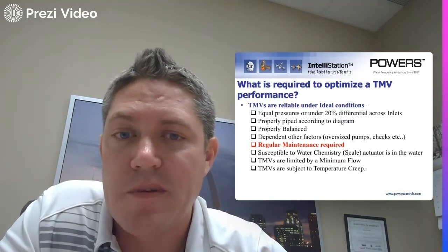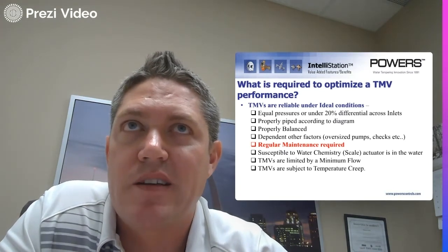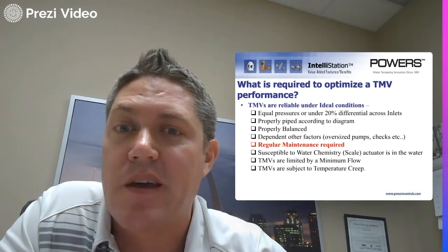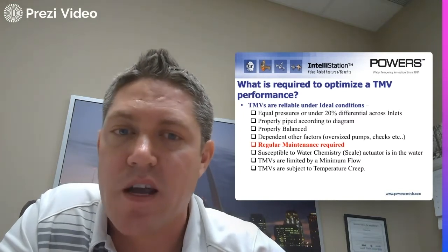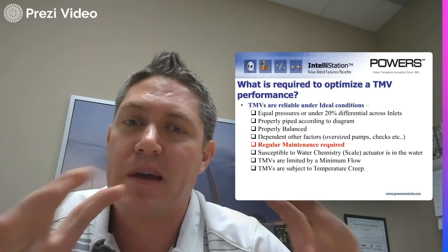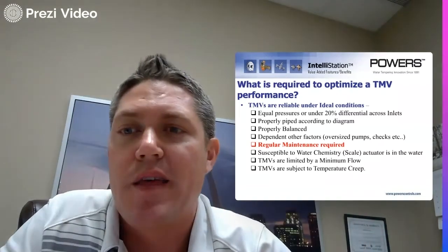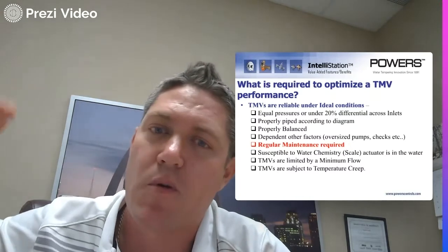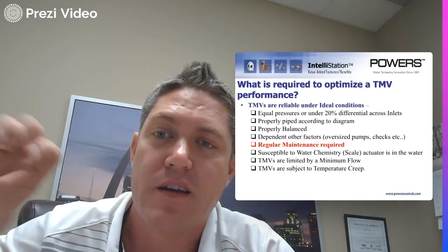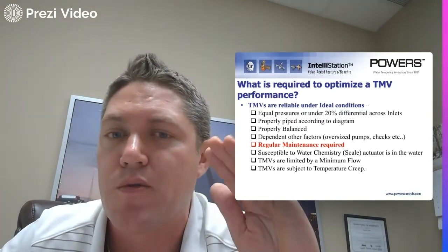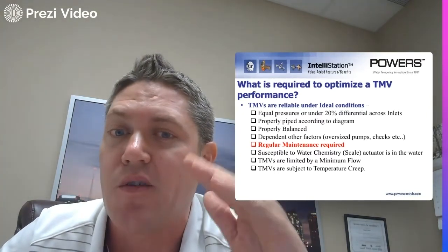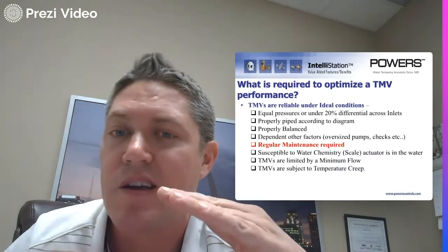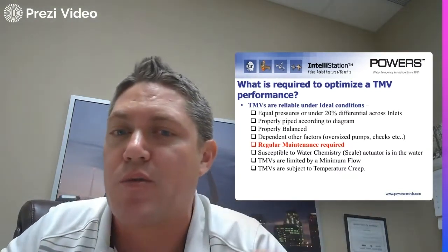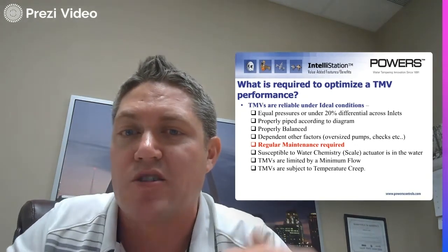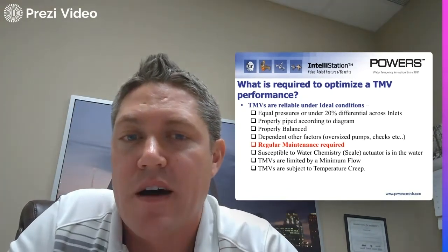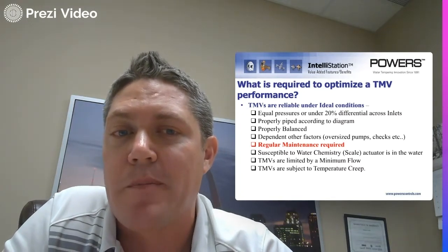Minimum flow with thermostatic, okay? So if you have a building that's going to have times of higher demand, but then also times where there might only be one or two faucets running, typically you're going to have to see a big mixing valve paired with a small mixing valve. That way, those are separated on the outlet side by a PRV, and you set a pressure there. And so all flow will go through the small mixing valve until there's enough demand downstream that there's a pressure loss. Then that PRV will open and allow flow to go through the large diameter mixing valve as well. So a high-low system with two valves in it may be necessary when you're talking about thermostatic master mixing valves.